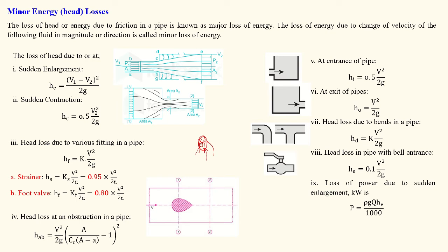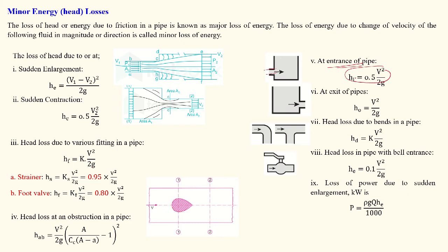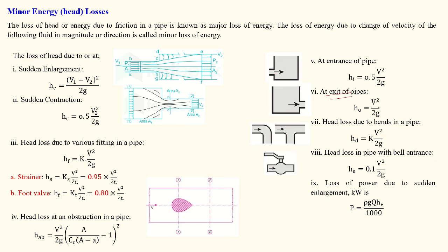For various fittings, the head loss formula is: hf = K·V² / (2g). For a strainer, Ks = 0.95; for a foot valve, Kf = 0.80. At the entrance of a pipe, K = 0.5, and at the exit it is similar. Head loss due to bends, T-joints, and other fittings uses the same formula. For a pipe with bell entrance, the formula gives: hf = 0.1·V² / (2g).